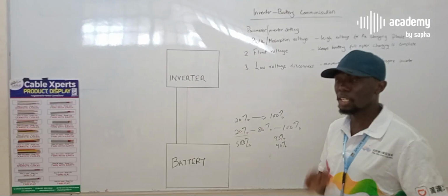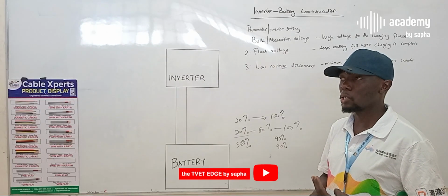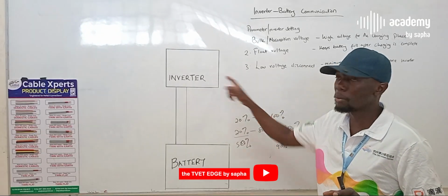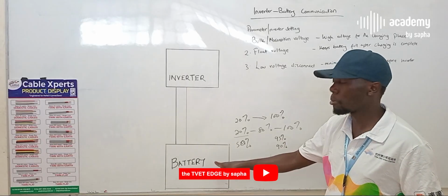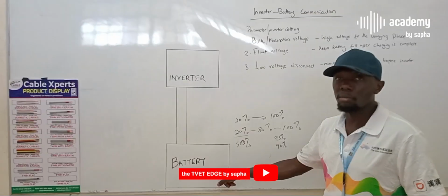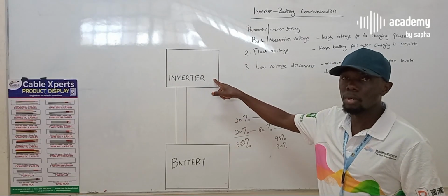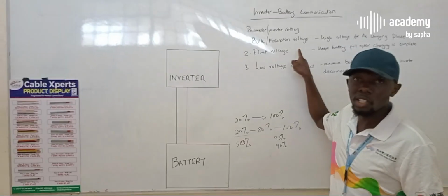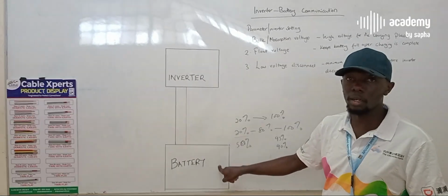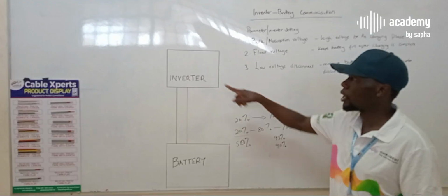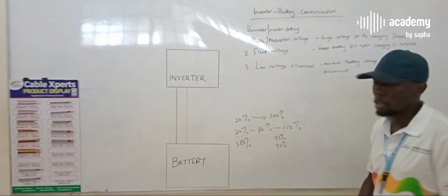So for example, if the inverter has been built to charge gel batteries and you are linking it to a lead acid battery, if the pre-programmed inverter parameters are a bit off or way off, over time you'll see that your batteries are suffering, not because you are over exploiting them, but because the inverter is not maintaining a proper charge and discharge profile for that particular battery. So it's essential for students to understand the role of this communication protocol in PV systems.